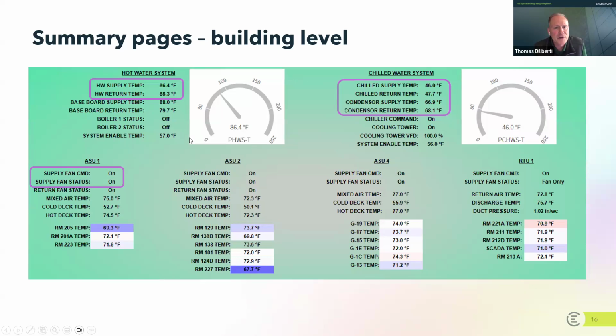That's important because it allows you to look at things like this hot water supply temperature and hot water return temperature and understand what should be happening. On a mild day, the water that's going out to the building and the water that's returning should not have much of a temperature difference, or delta T. What's interesting is the water going out is actually cooler than when it's returning. It's warmer coming back, so this is unusual. This might suggest that one of these sensors is reading a little bit wonky. Nothing crazy here, but look at these hot water temperatures to make sure they make sense with the conditions in your building. Likewise, these chill water temperatures over here.